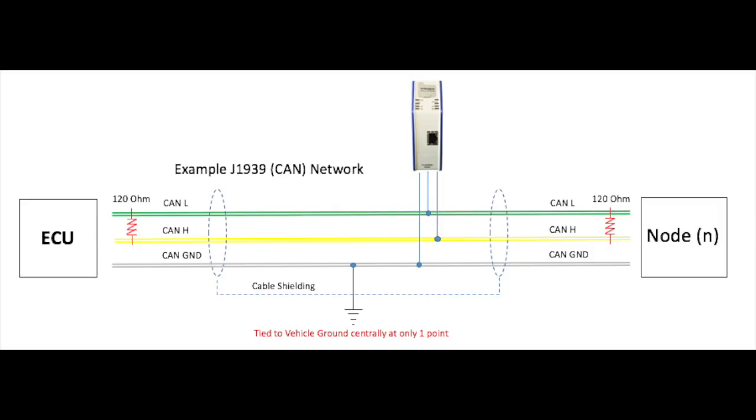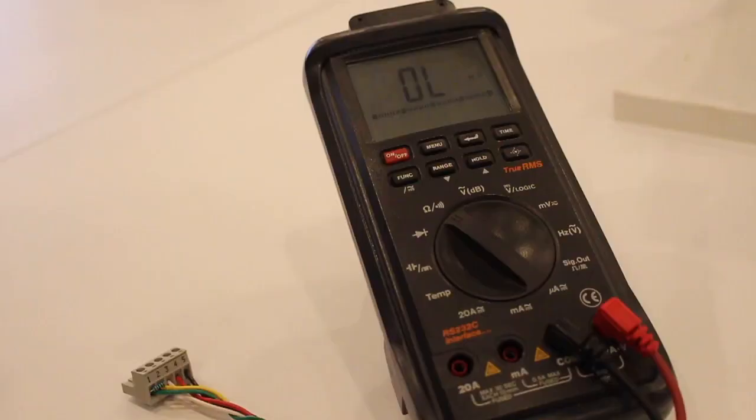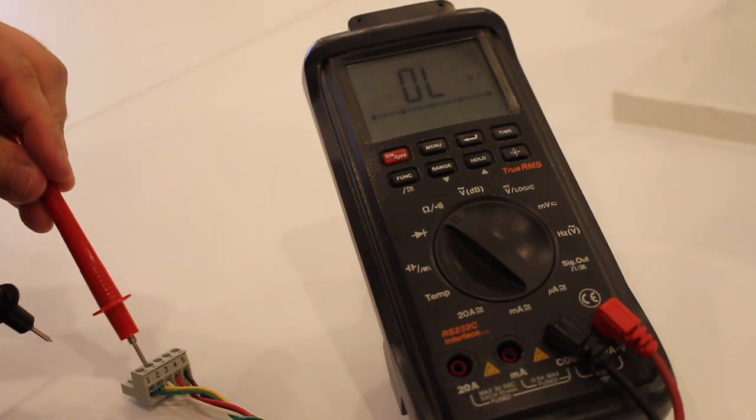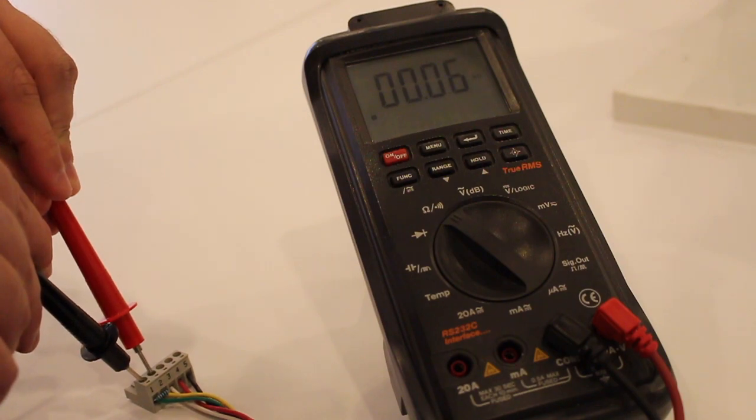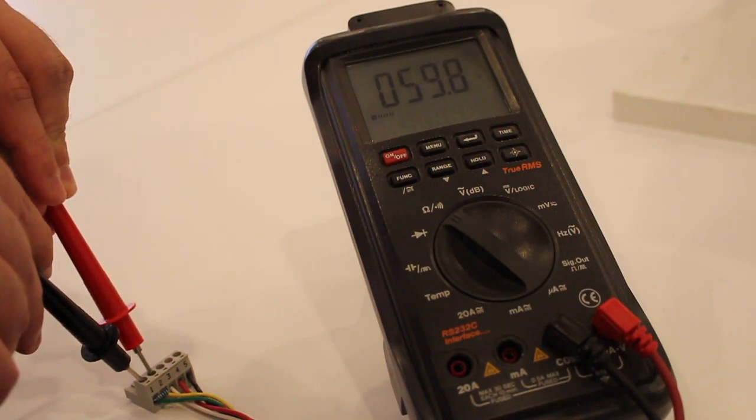Please note that the Bridgeway device does not provide CAN network termination internally. Proper termination should be confirmed during installation. There should only be two 120 ohm terminating resistors on the network, and they should be placed at the ends of the network. To check if your network is terminated properly, measure the resistance across CAN high and CAN low with all network-connected devices powered off. A properly terminated network will measure approximately 60 ohms.